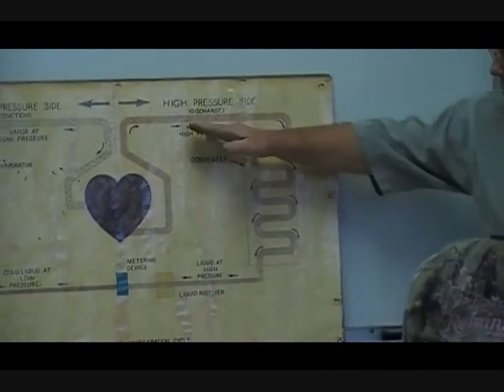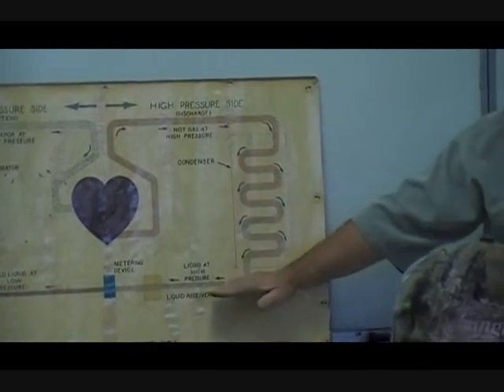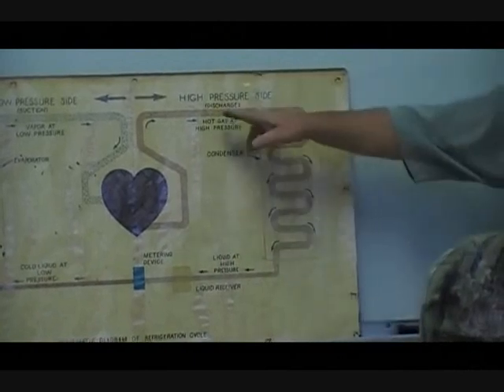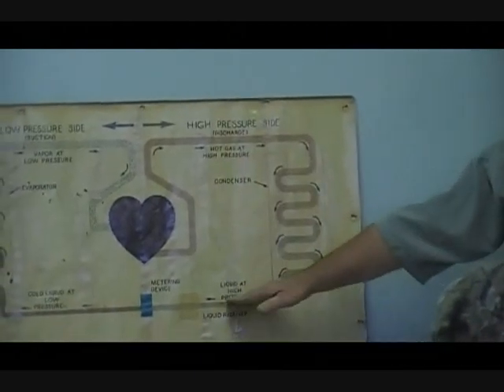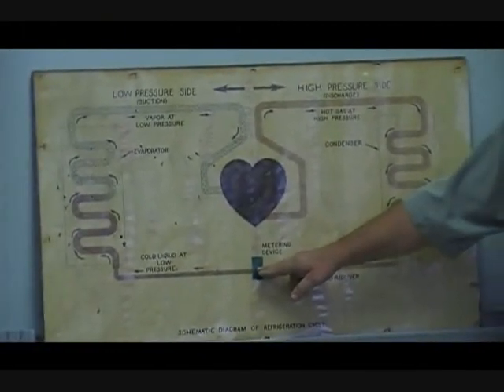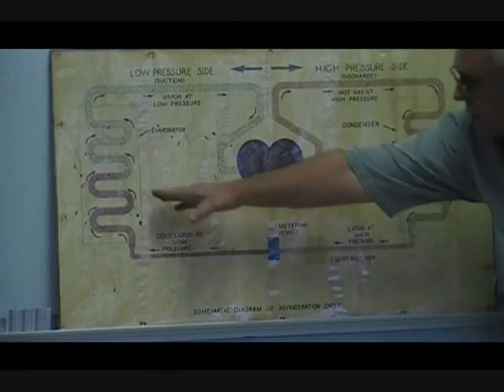It's a high-pressure liquid. The pressure has not really changed that much other than the loss through the piping itself. So basically the high-side pressure is going to be the same at the discharge as it would be at the liquid line. The only difference is here we have gas, here we have liquid — the heat has been removed. It then enters the metering device. The metering device throttles the refrigerant — it's a restriction in the line. A simple definition of a metering device: it's a restrictor.